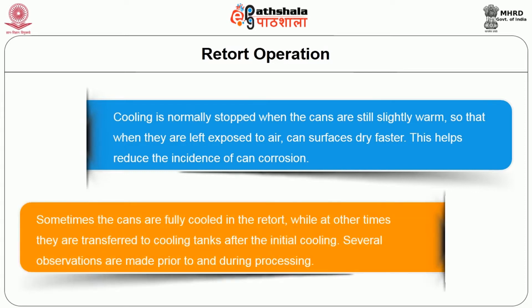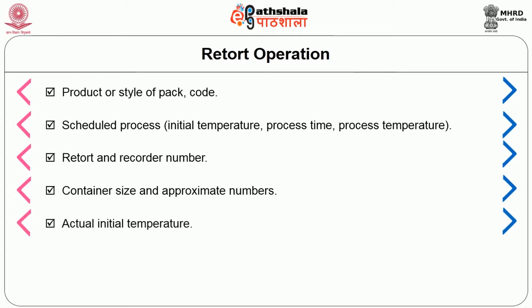Sometimes cans are fully cooled in the retort, while at other times they are transferred to cooling tanks. After the initial cooling, several observations are made prior to and during processing. Typical information collected includes product or style of pack code, scheduled process, retort and recorder number, container size and approximate number, actual initial temperature, time steam on, vent closing time and temperature, come-up time, steam-off time, actual processing time given and temperature, and MIG and recorder readings.